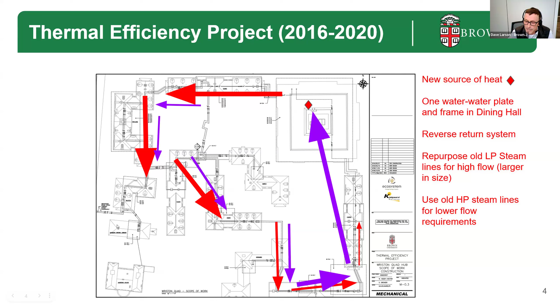The cost was way less than it would have been if we had run new medium temperature hot water lines through that whole loop. The disruption was minimal. We had very little drilling, welding, dirt, and noise. Since these dorms are used year round, we have a robust summer program, and that's a problem—you don't want a lot of drilling and people traipsing in and out of dorms when you have teenagers there.